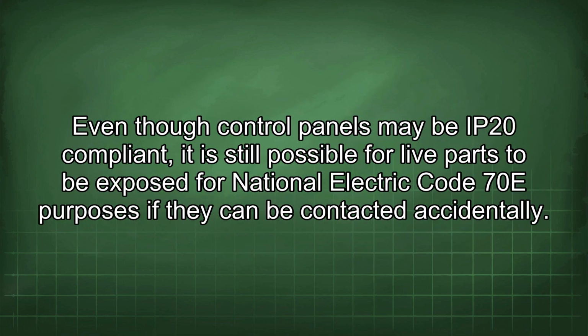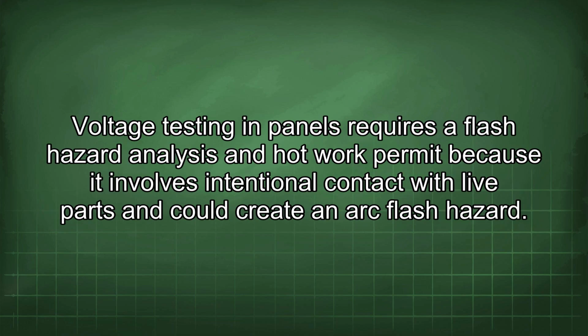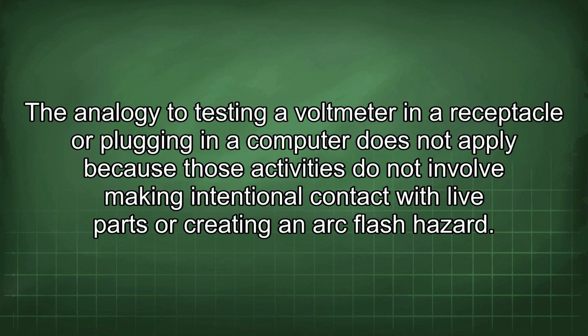Even though control panels may be IP20 compliant, it is still possible for live parts to be exposed for National Electric Code 70E purposes if they can be contacted accidentally. Voltage testing in panels requires a flash hazard analysis and hot work permit because it involves intentional contact with live parts and could create an arc flash hazard. The analogy to testing a voltmeter in a receptacle or plugging in a computer does not apply because those activities do not involve making intentional contact with live parts or creating an arc flash hazard.